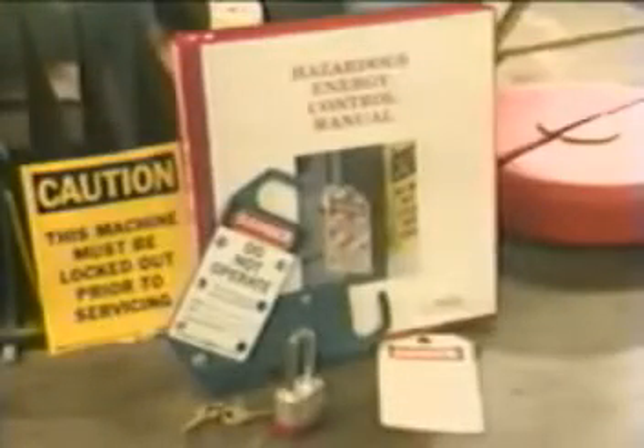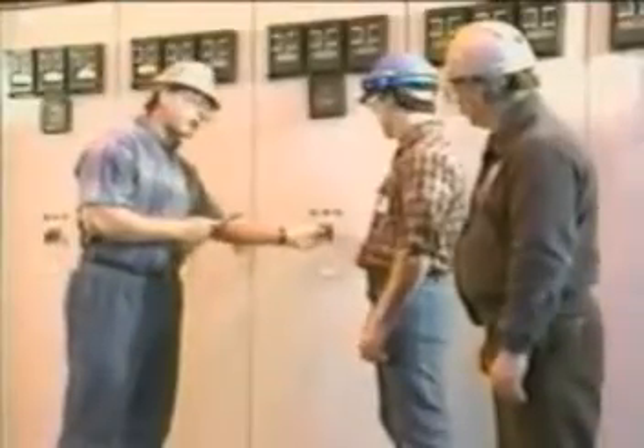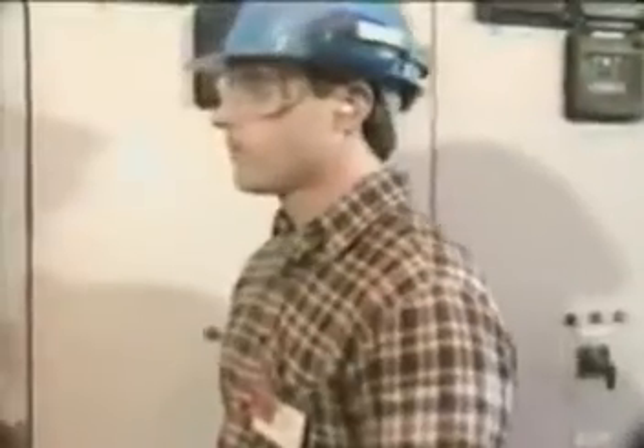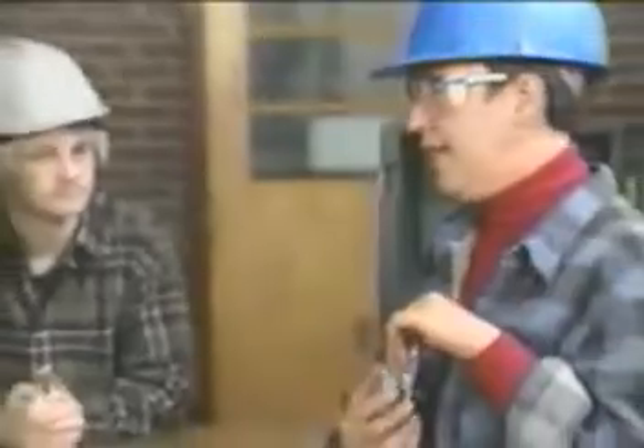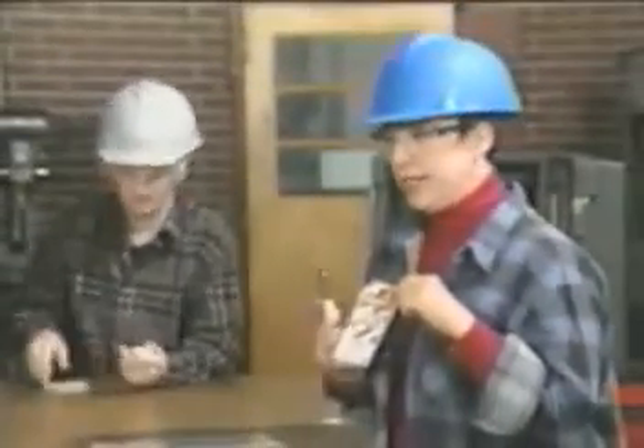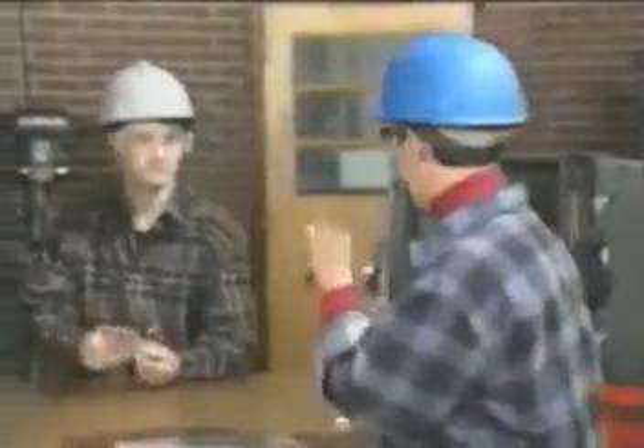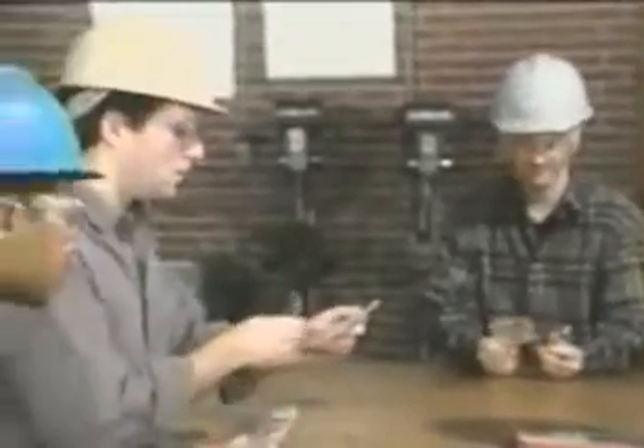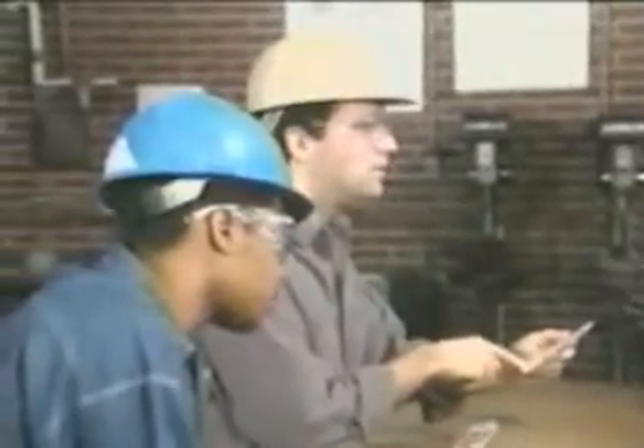OSHA considers the use of a lock safer than using just a tag. However, tagout can be practiced alone as long as your employer can show that tagging out provides the same level of safety that a lockout system provides. But special additional training is required when tags are the only form of protection. This training will inform you about the limitations of tags and the importance of obeying their warnings. Often companies will require both lockout and tagout. Regardless of whether your employer uses lockout, tagout, or both, make sure you understand and follow the correct procedures for your particular organization.